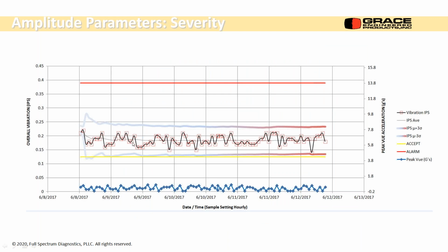Okay. Oh, the other thing, we can trend more than one parameter. Okay, I mentioned earlier the Grace nodes, they have a triaxial MEMS accelerometer in them. 2 of those axes, the X and Y directions, I believe the frequency range is 1,000 hertz. The third direction, they're starting to change out those and make that, I think, an 8,000 or 9,000 CPM or hertz signal.